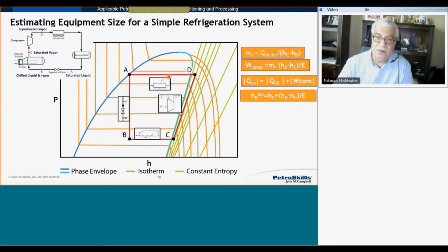The condenser duty calculation is easiest. This is a closed loop system. Suppose this is my loop. In a closed loop, I add heat from the process gas to the system. I add energy to compress the gas. Now I have to remove the heat from the condenser. So energy in, which is the sum of the compressor and chiller energy I'm putting in, must equal energy out, which I remove as heat through the condenser. So, in absolute form so I don't goof up tracking the sign, the absolute value of condenser duty is equal to the absolute value of the chiller duty plus the absolute value of the compressor power requirement.